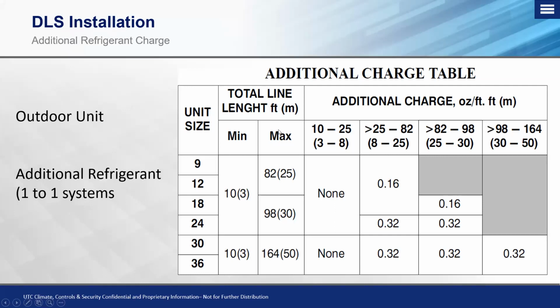Maximum will depend on the tonnage that you're working with. So you can see a 9 and a 12,000 single zone only has a maximum of 82 feet, while a 30 or a 36,000 BTU system can get up to 164 feet. So again, this is something you need to make sure that you look in your installation and service manual to know what your maximum piping length is, and that depends on your tonnage.